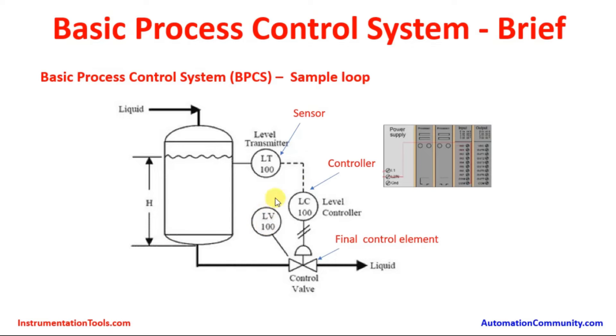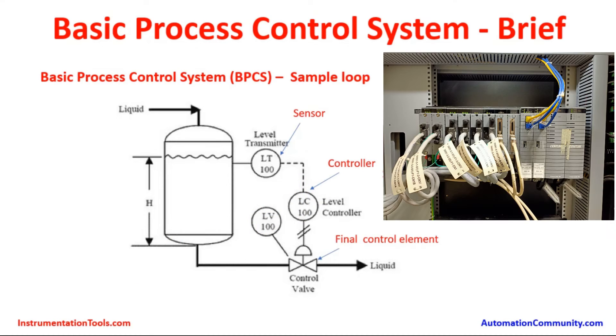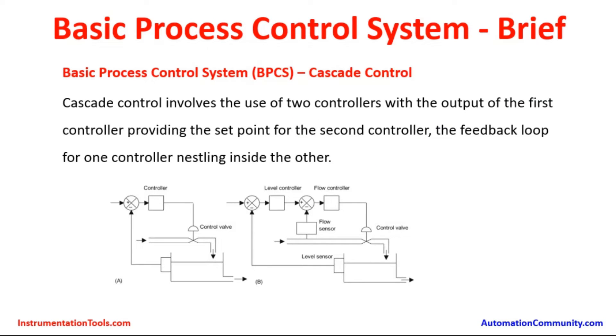Pictorially it is represented as a controller. Basically it looks like this, wherein the controller will have a power supply unit, a central processing unit with microprocessor-based controllers, and input and output modules, etc. DCS and BPCS are used alternatively but both represent the same thing. Cascade control involves use of two controllers, with the output of the first controller providing a set point for the second controller, with the feedback loop of one controller nested inside the other.